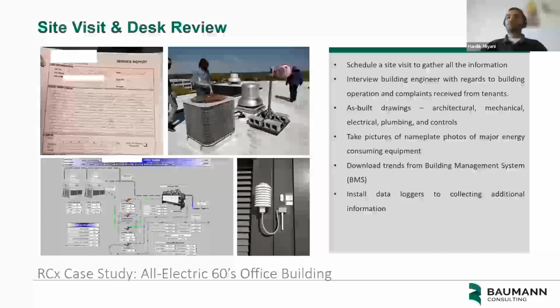So during this audit, we asked several questions to the building engineer. Some of them can be like, does the building engineer receive any sort of hot or cold complaints from the tenants in the space? Interestingly, the engineer did receive several complaints from the tenants, especially for the tenants facing on the south side of the building. The building engineer was receiving a lot of hot calls with regards to the solar heat gain and the perimeter heating that was happening.